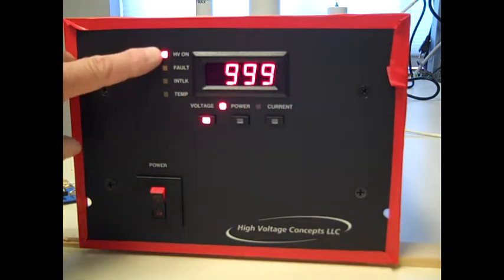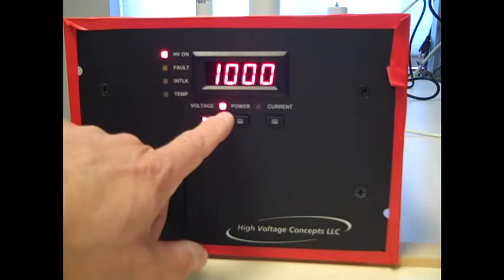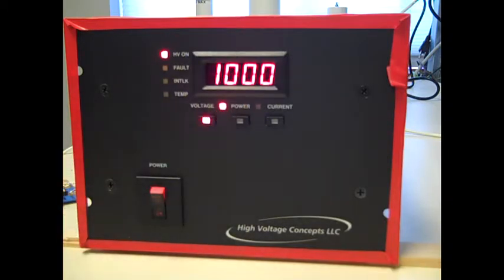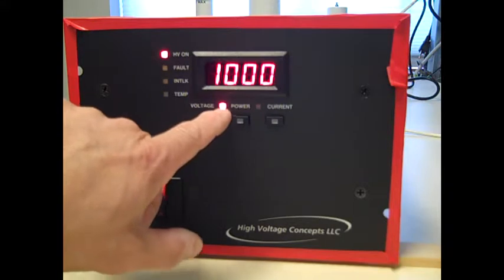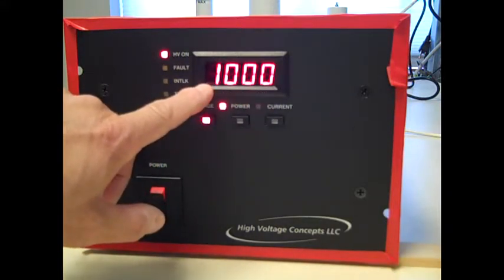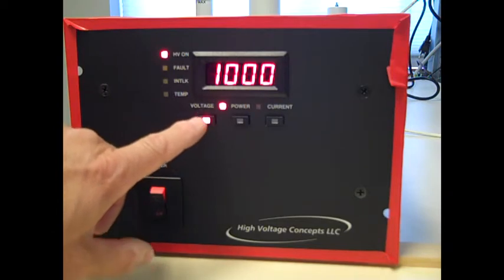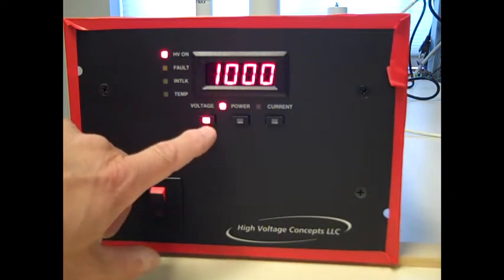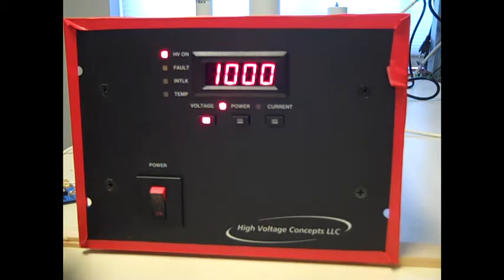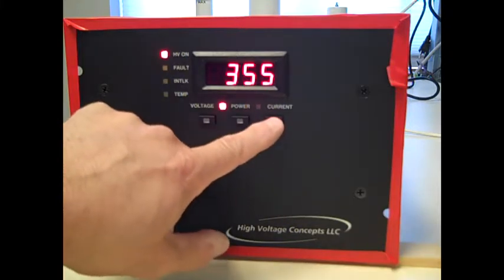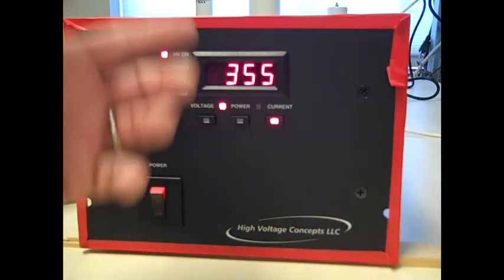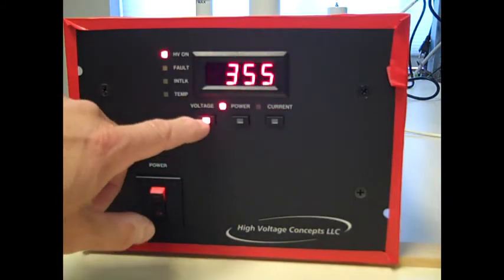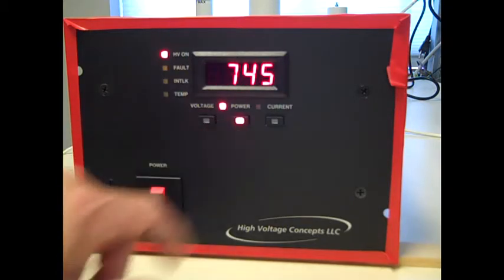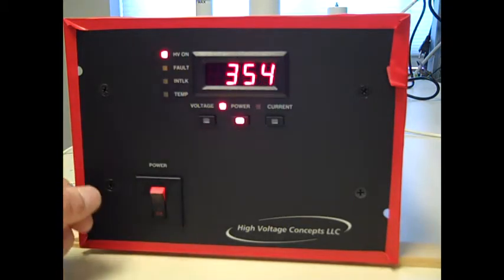So the high voltage light comes on, and you can see that even though we're in the power mode, it is voltage regulating because it has hit the limit of the capabilities of the power supply at 1000 volts. So we're looking right now at the voltage meter. It's voltage regulating even though we're in power mode because it's hitting the limit. And now let's look at what the power is. The power is 355 watts, and the current is 355 milliamps. Obviously 355 milliamps times 1000 volts is 355 watts.